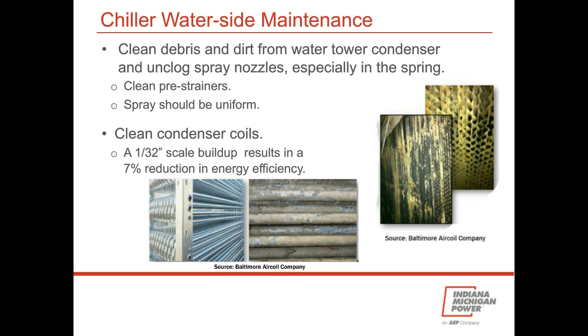Again, we have the water loops, a lot of water involved with chillers. You want to clean condensers. There's filter media shown here on the right. You can see how badly it can get gooped up here. Also, there's strainers at the bottom of the pan. It's trying to strain out the big leaves and dirt, etc. You have spray nozzles at the top. We'll see an example out here in a minute. That should be uniform. All the nozzles should be working. And so those are things to look at.